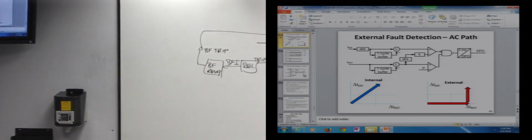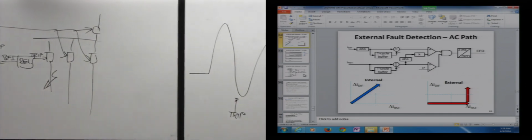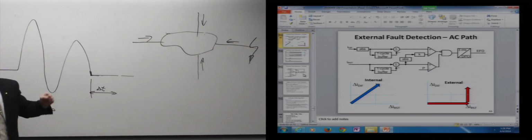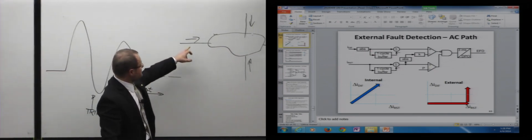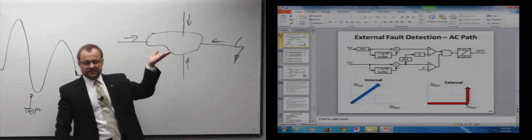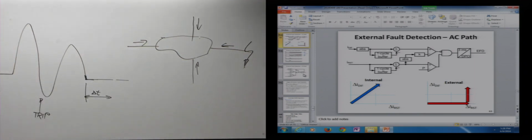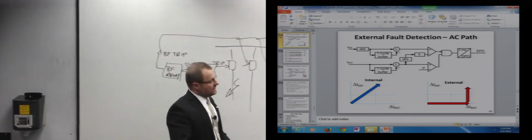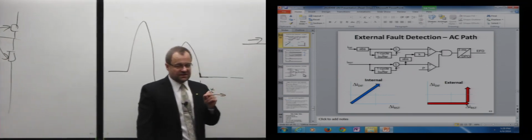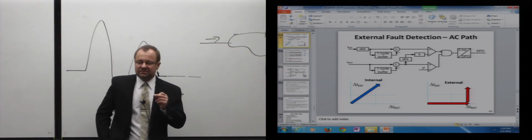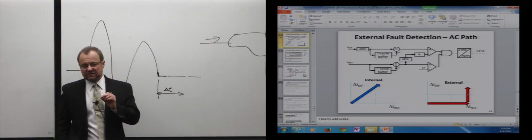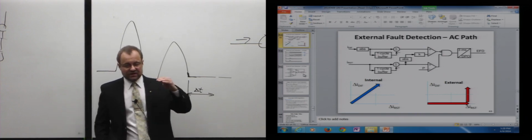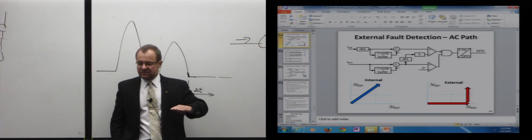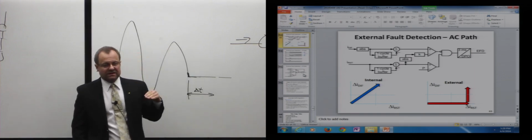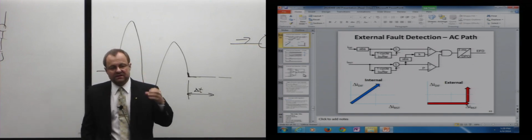What happens if I have an external fault? So let me remove that fault and put it here. The fault current rushes towards the fault, correct? So what happens to all those currents? They go up immediately, right? So this is where the restraining current will increase. What happens to my differential current? The assumption is that a CT, even if it saturates severely, saturates only after a few milliseconds. It has a room of a few milliseconds, because what you have to do to saturate a CT is move its flux from a very low value all the way to saturation. And this cannot happen instantly, even if you put a lot of current into that CT.